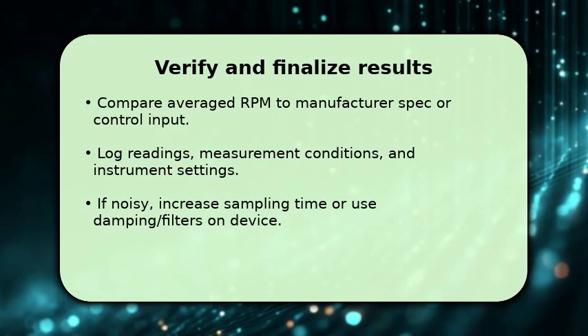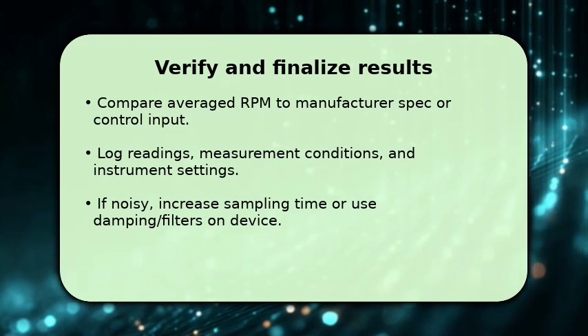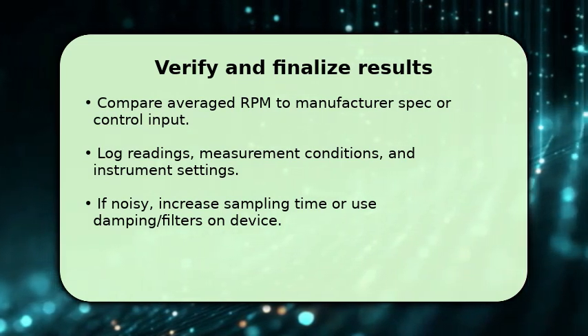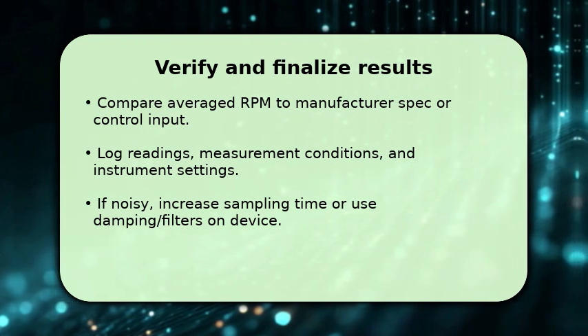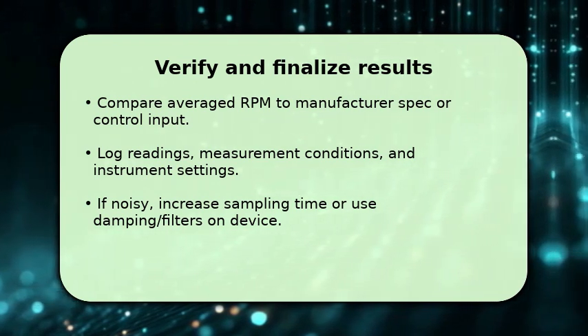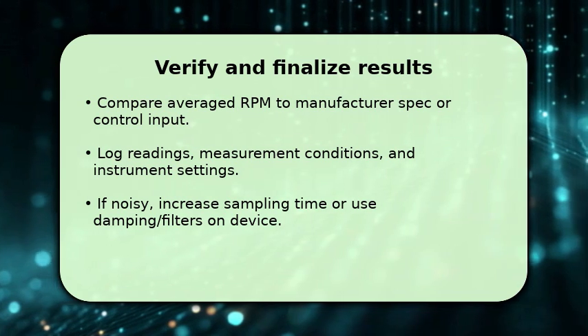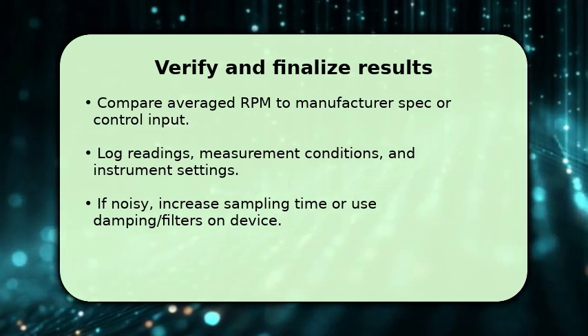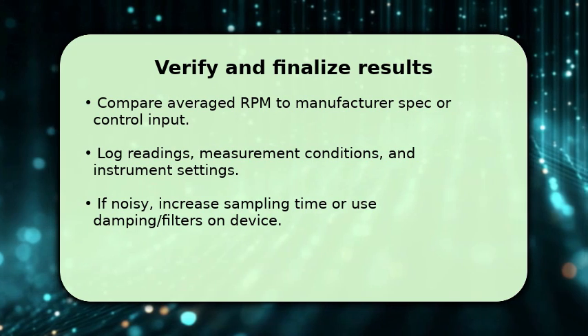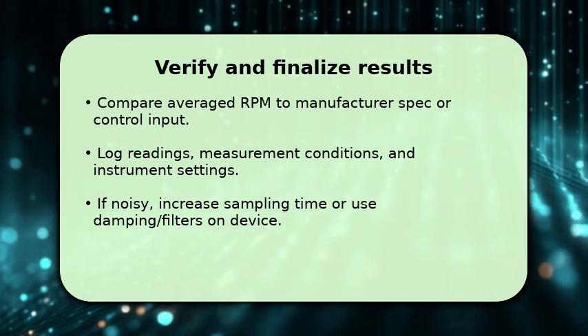You finish by comparing the averaged RPM against the expected value or specification and logging the exact reading with conditions: load, temperature, and instrument mode. If readings fluctuate, try longer sampling or enable the tachometer's smoothing filter to reveal the steady-state speed.